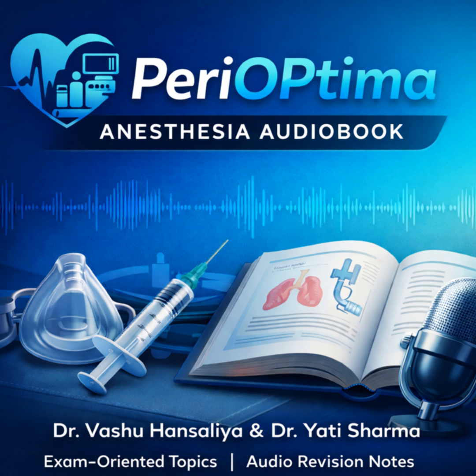What's the downside? The main downside is that the cycle is very long, sometimes many hours. And crucially, you need a long period of aeration after the cycle is finished. ETO is toxic and carcinogenic, so any residue must be allowed to dissipate completely before the item can be used on a patient. And then there are the liquids. Glutaraldehyde, we've all seen those trays of blue liquid in the OT. Cidex, it's typically a 2% solution.